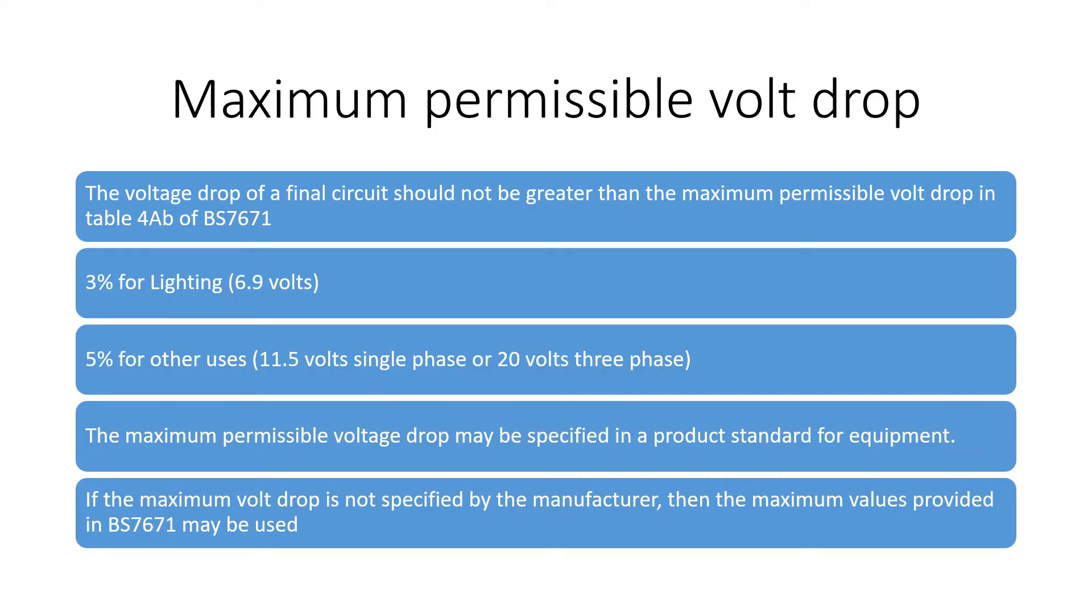So the requirements of voltage drop are found in Appendix 4 of BS7671, which requires that the voltage drop between the origin of the installation and the load should not be greater than the values in Table 4AB of BS7671, which are 3% for lighting and 5% for other uses. This is for low voltage installations supplied from the public supply. This is to ensure that the voltage is not so low that it would impair the proper functioning of the equipment.